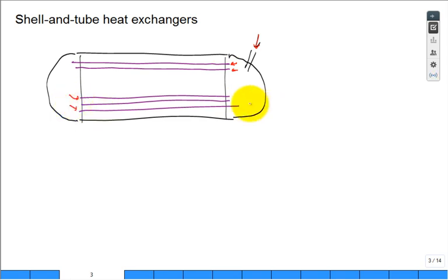And go out. Maybe you have a plate that splits here, prevents the short circuiting in another outlet, and so the fluid eventually goes in and leaves on the same end. Pretty convenient. You could unbolt this and maybe put in a tube cleaner.